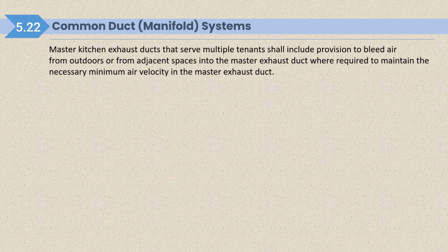Common duct manifold. Master kitchen exhaust duct that serves multiple tenants shall include provision to bleed air from outdoor or from adjacent space into the master exhaust duct where required to maintain the necessary minimum air velocity in the master exhaust duct. So here it is talking about mainly the food court type of arrangement where we installed one master kitchen exhaust duct and all other small restaurants connect their duct into that master kitchen exhaust duct. In master kitchen exhaust duct there is a provision of bleed air supply air that ensure the minimum air velocity in the master exhaust duct.